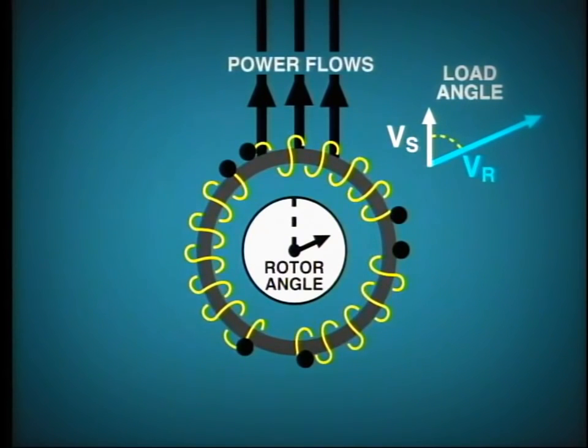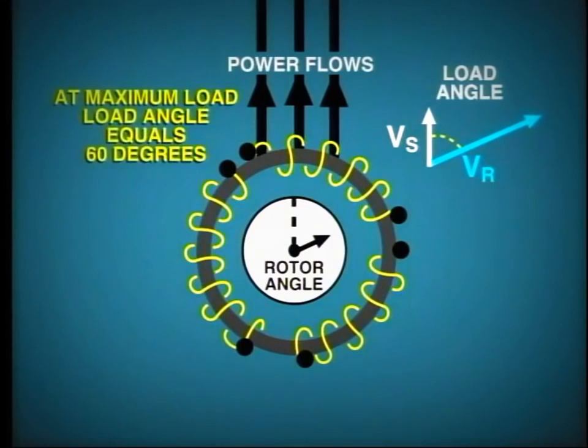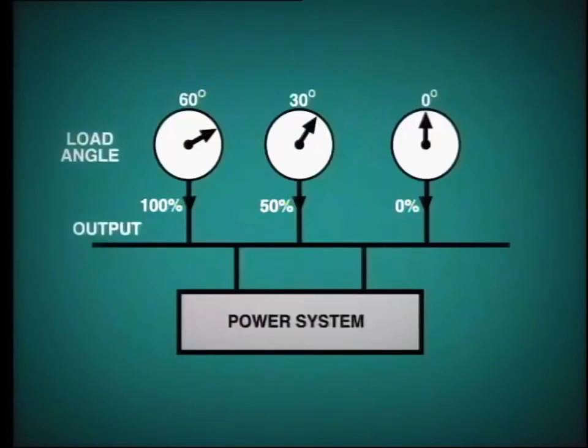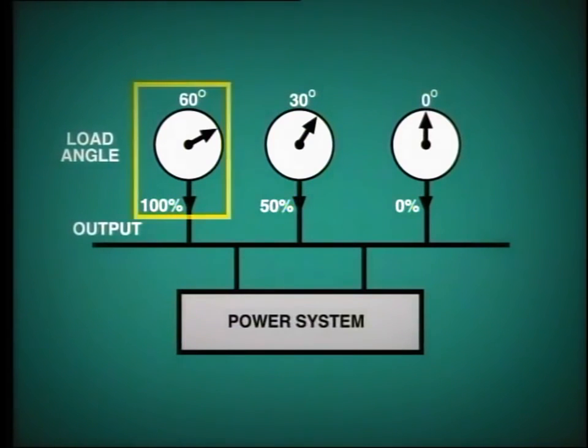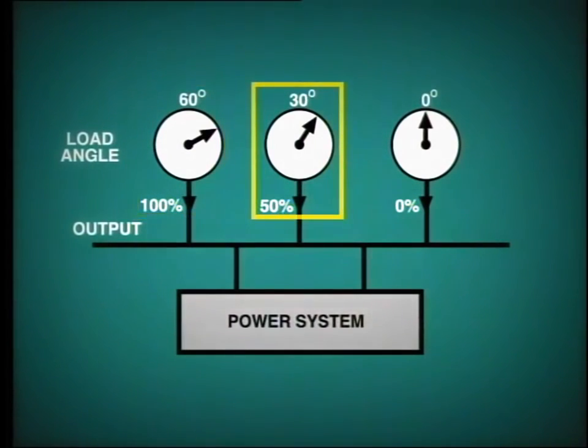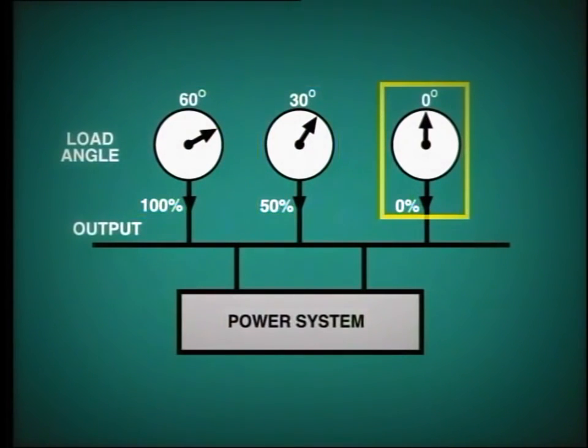In each case, the rotor settles down to its new condition and continues to run at the new load angle. At maximum load, the load angle will probably be about 60 degrees. So now you can see if we have, say, three units in parallel on a common bus: the unit generating at 100% capacity will have a load angle of about 60 degrees, the unit at 50% output will have a load angle of about 30 degrees, and the unit at zero load has a load angle of zero degrees.